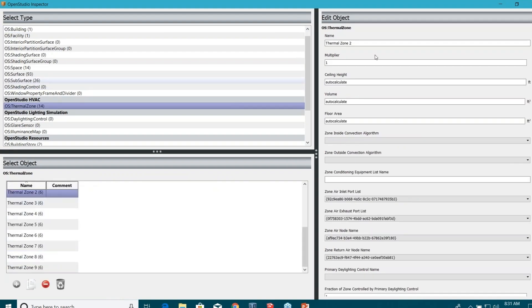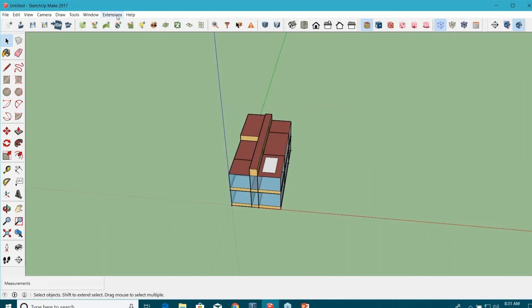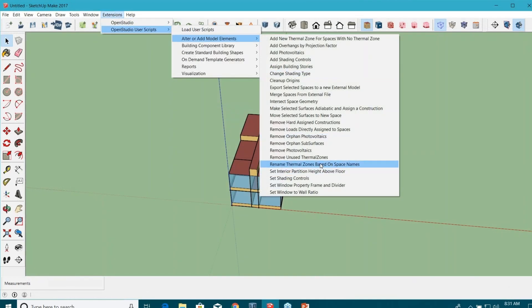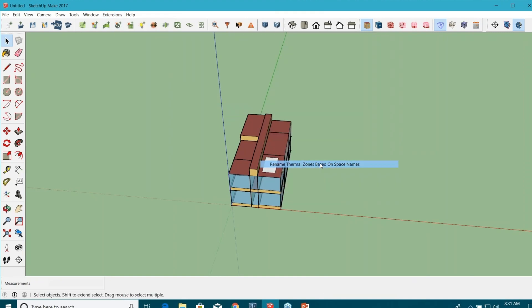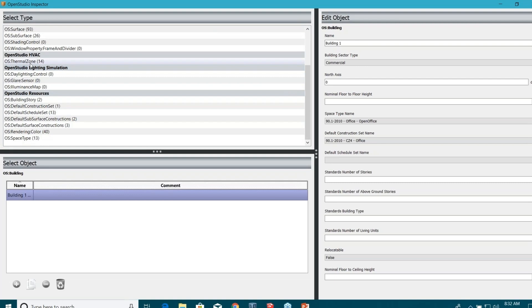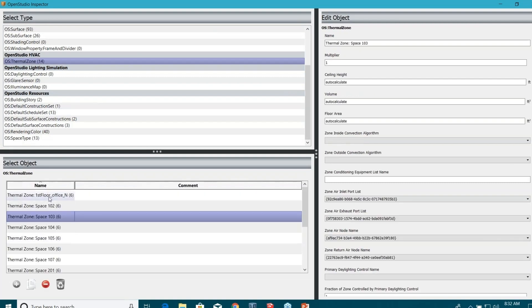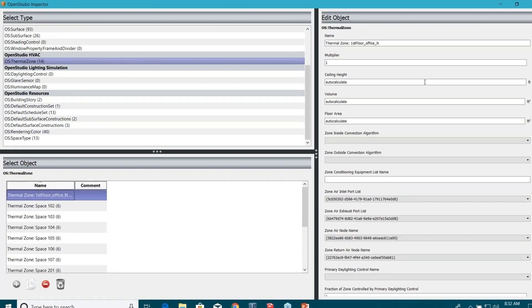Again, you can see they have very generic names. So I like to run another script here, which is 'rename thermal zones based on space names.' And what happens now — you can see my thermal zones have the exact names I gave to my spaces. Now I know that for this thermal zone, where do I need to go in case I need to make some changes to internal gains. This thermal zone is connected to 'first floor office,' and that's where I need to go to fix unmet load hours or anything.